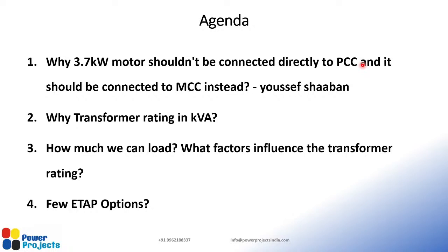But you need to withstand and break a fault current of 75 kiloamps or 100 kiloamps, depending upon the PCC short circuit current, which increases the cost of the circuit breaker and increases the dimension of your PCC. It also complicates the arrangement of your PCC, and to an extent it destroys the coordination as well. That's the real reason why you should not connect small capacity motors directly at the PCC. Instead, you push the small capacity motors to a downstream MCC, a motor control center. I guess that's clear. Let me look at some questions.